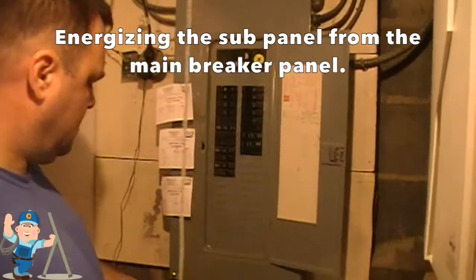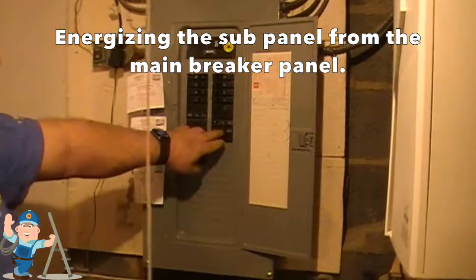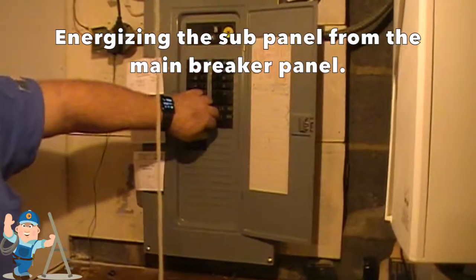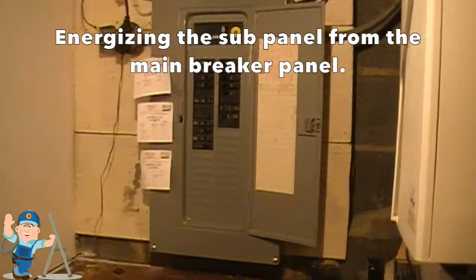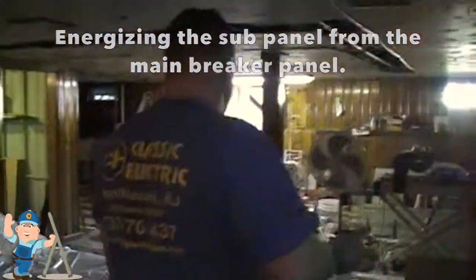Now we're all done with the panel, and we've installed the circuit breakers. I'm about to flip on the main for that sub panel and go back there to check the voltage and make sure it's correct before energizing each of the circuit breakers in the panel. This basement will be redone shortly from what I understand.